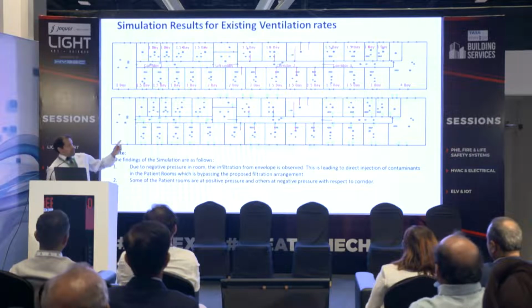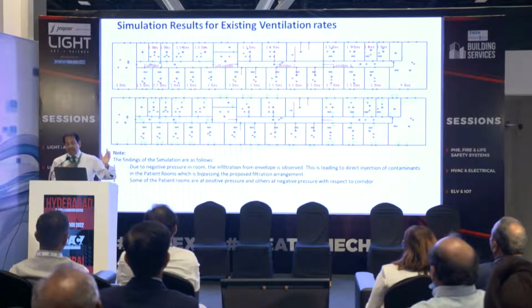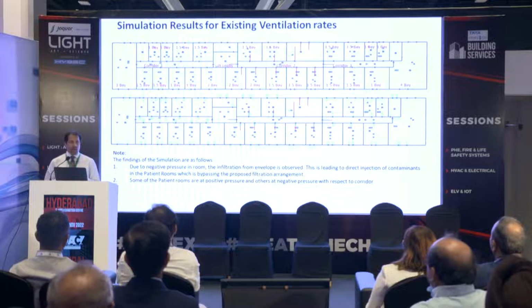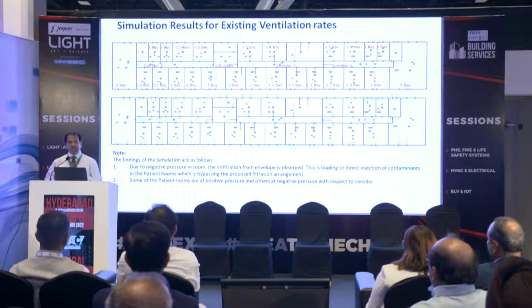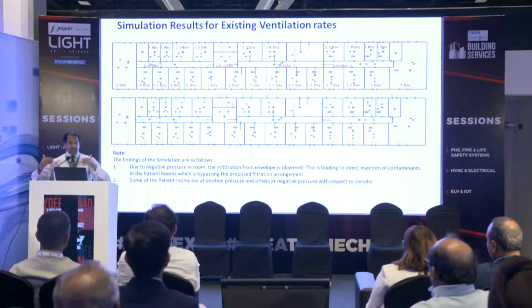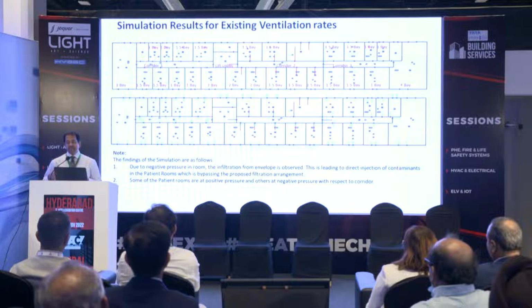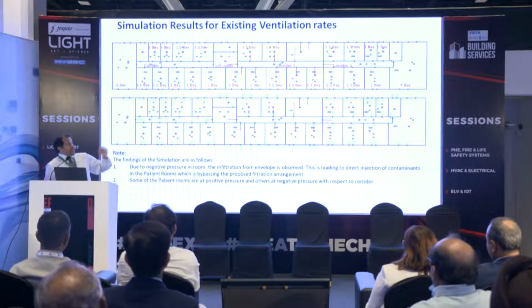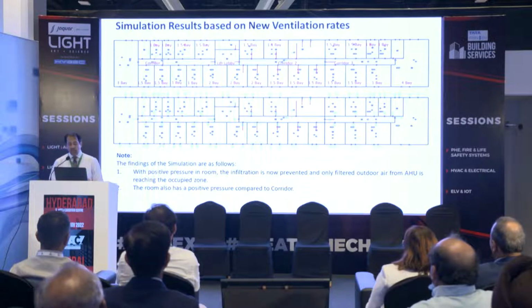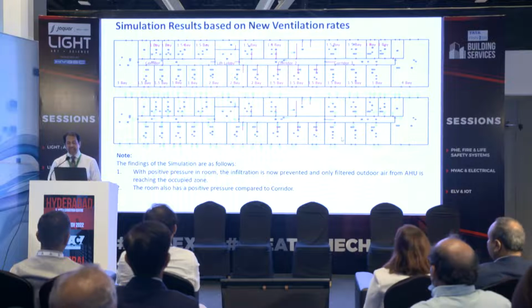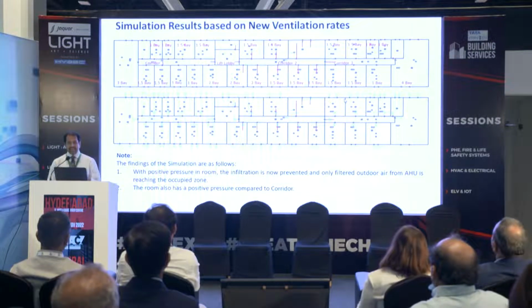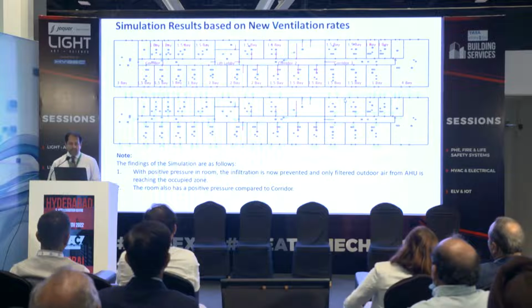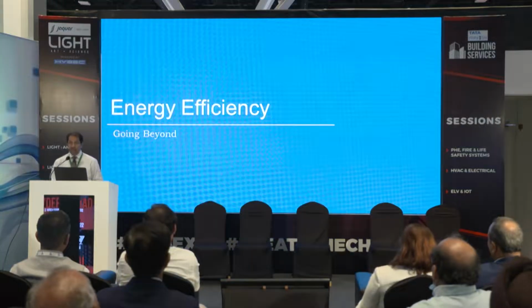What happened in this project was, if you want good indoor air quality, you have to maintain positive pressure compared to the outside, so that outside air doesn't come in. The air pressure relationships — the amount of fresh air being injected — become key, and that's what is being tested here, to get exfiltration as a design rather than infiltration happening into the building. We need to go beyond this.